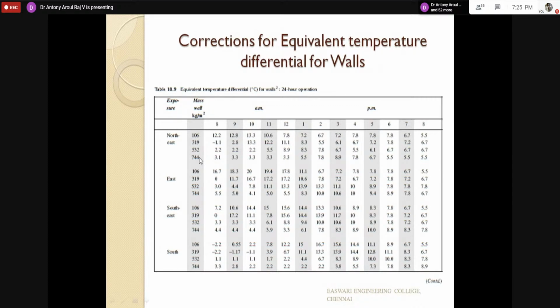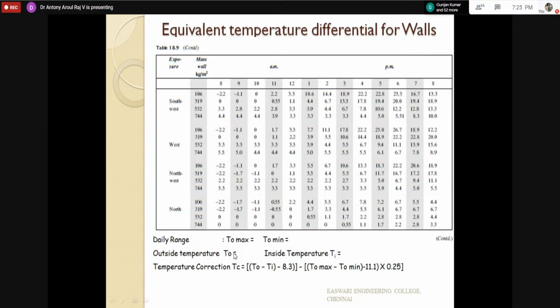So we have varieties of material: lightweight construction and heavyweight construction. This equivalent temperature difference is given for each direction, and it is not connected with the radiation received at a place, but with the outside and inside conditions. So we do a correction based on the daily range—this is very important. The daily range is connected with radiation, because at the equator the temperature rise will be much higher compared to other places.